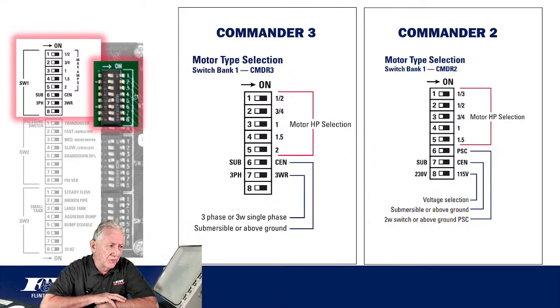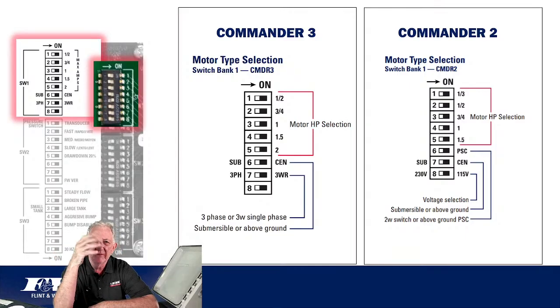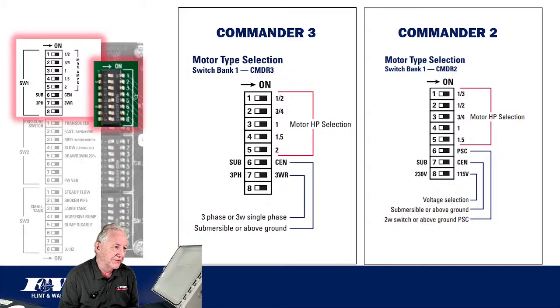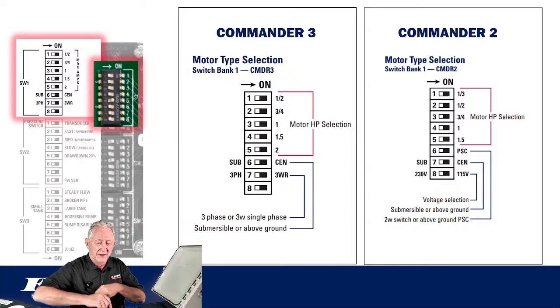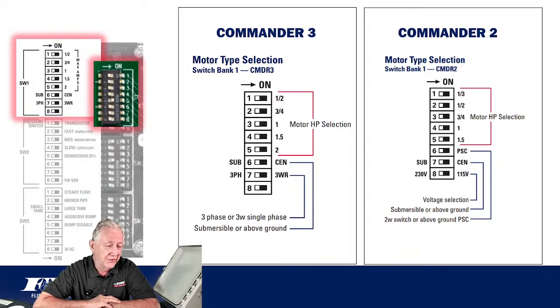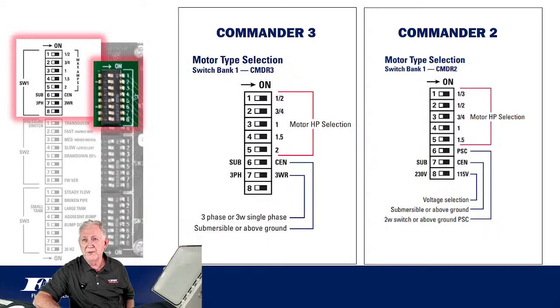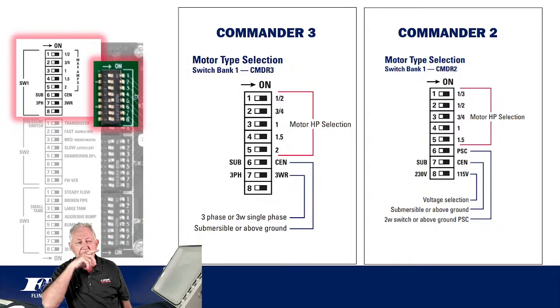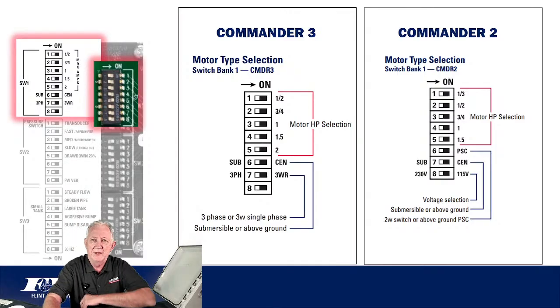So again, if this were a submersible pump, you would select your horsepower up here based on the 2-wire drive. Once again, that's position 6 in this case. If this is a submersible pump, there's nothing you're going to have to do with that. We're going to move that when we get back to a centrifugal motor. I'll circle back on that in a second. But position 7, once again, we're selecting between a submersible pump or a centrifugal pump. And with the 2-wire drive motors, particularly in that 1/2 horsepower, this is the only one where you would have a choice between 115 volt and 230. I'm going to guess the majority of the time that's going to be a 230 volt model, with the exception of the occasional 1/2 horse that may be 115 volt. But those are the primary differences up there at Bank 1 between those two types of drives.